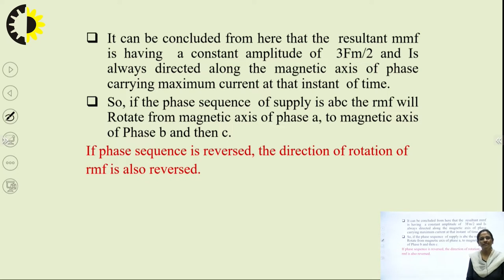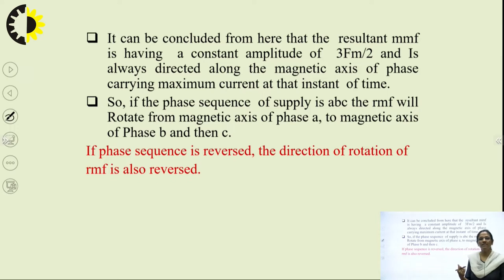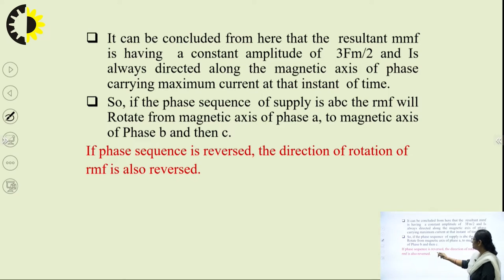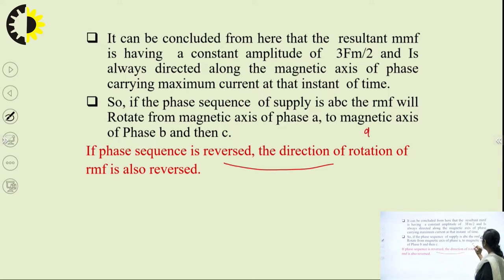If the phase sequence of the supply is ABC, the rotating magnetic field rotates from the magnetic axis of phase A to B to C. If we want to reverse the direction of rotation of the rotating magnetic field, we simply reverse the phase sequence. If the phase sequence is made ACB, the rotating magnetic field rotates in the opposite direction.